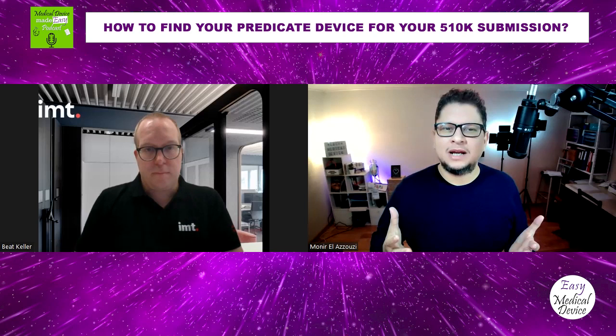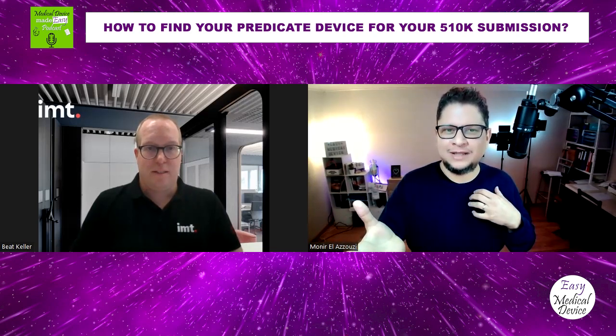So usually we are saying, oh, we should be the first on the market. I don't want to have competitors, etc. In this case, you want to have a competitor that already went through this and is already placed on the market. So you can compare yourself to this product and say, I am the same as this product. Exactly. If this product is on the market, I can be on the market. It's fine for me to be on the market. So this is mainly the idea here.